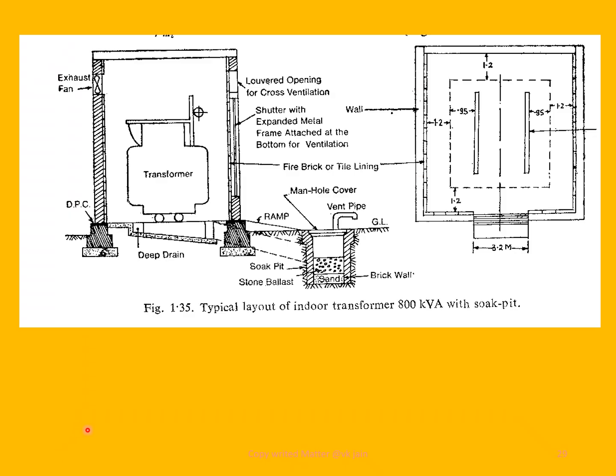Friends, this diagram shows the transformer oil drain. A drain has to be provided if the transformer contains more than 2000 liters of transformer oil.